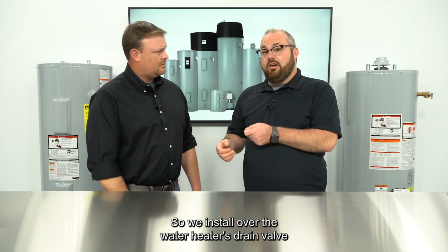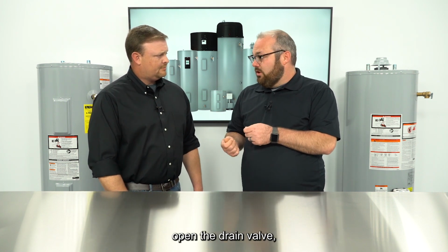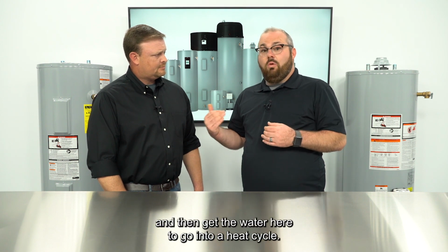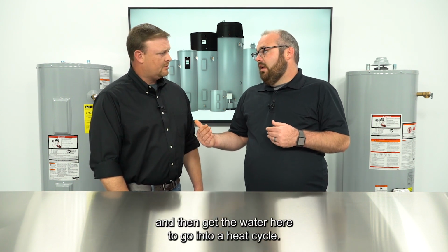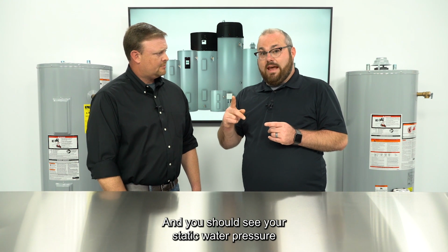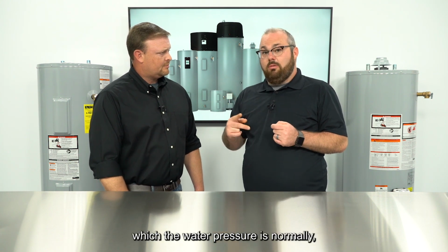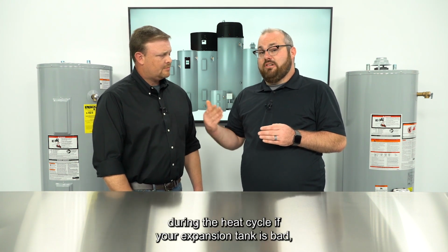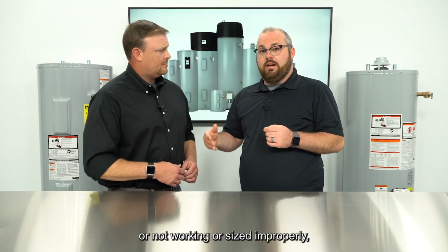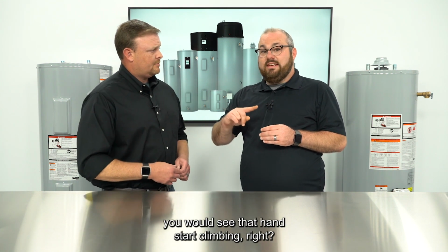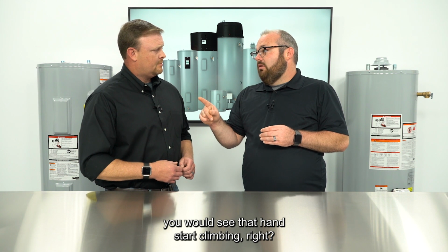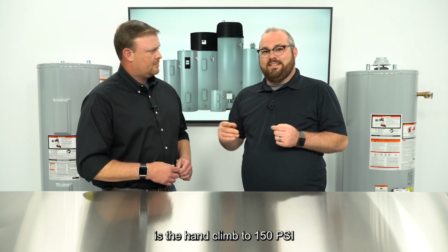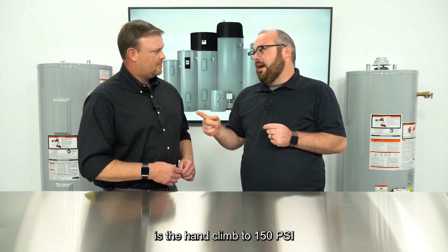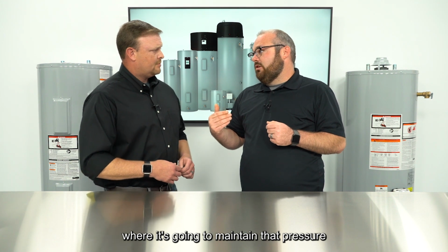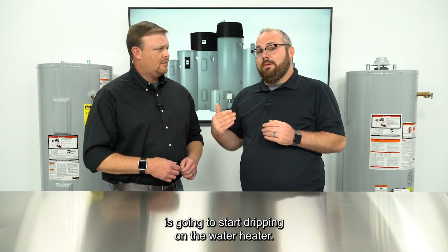So we'd install it on the water heater's drain valve, open the drain valve, and then get the water heater to go into a heat cycle. You should see your static water pressure, which is your normal water pressure, during that heat cycle. If your expansion tank is bad, not working, or sized improperly, you would see that hand start climbing. Typically the hand climbs to 150 psi, where it's going to maintain that pressure because the relief valve is going to start dripping on the water heater.